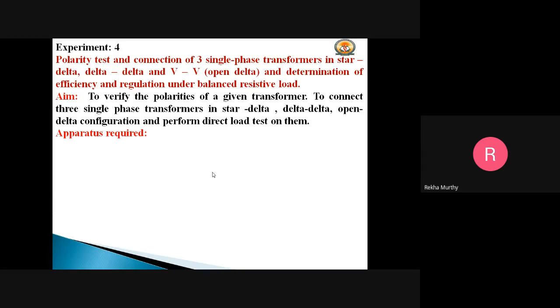So we are constituting a three phase transformer. Let's see the possibilities for connecting three independent single phase transformers to work as one three phase transformer. They can be connected in any configuration - star-delta, delta-star, star-star, delta-delta - depending on the load requirements. There are different possible connections for the three single phase transformers in a bank.